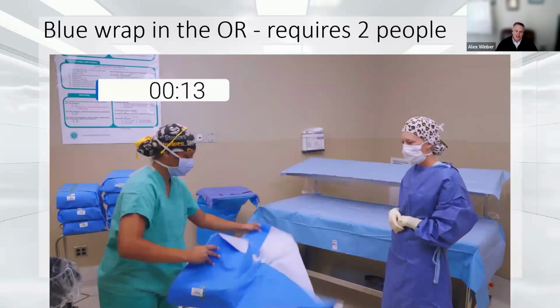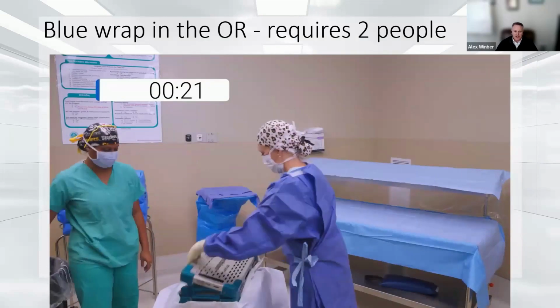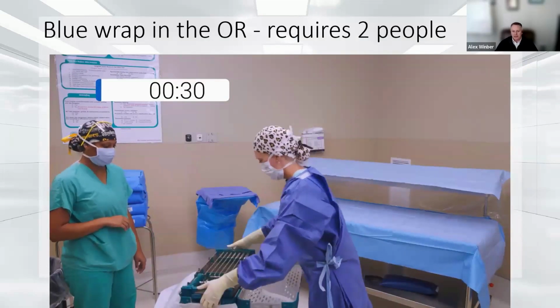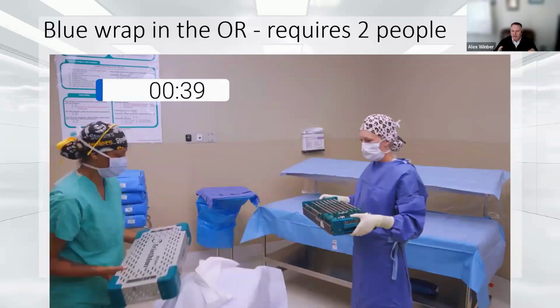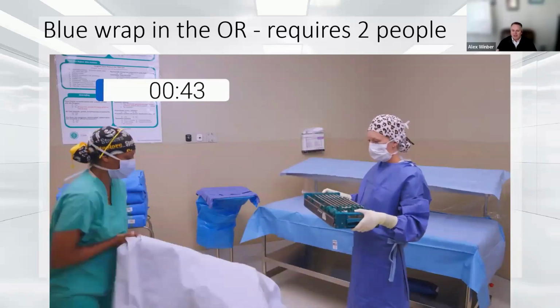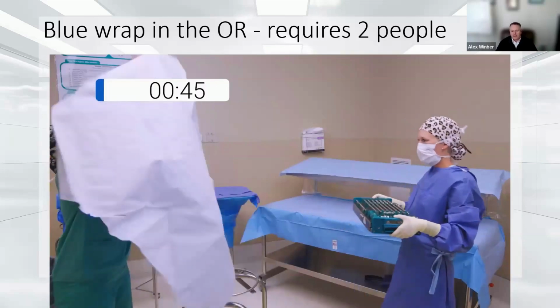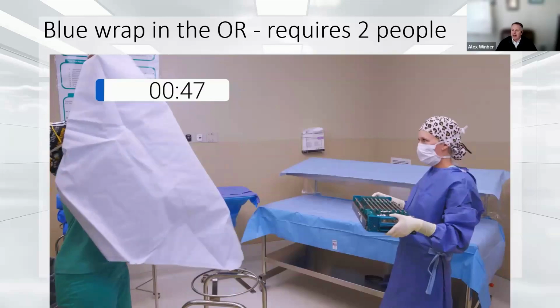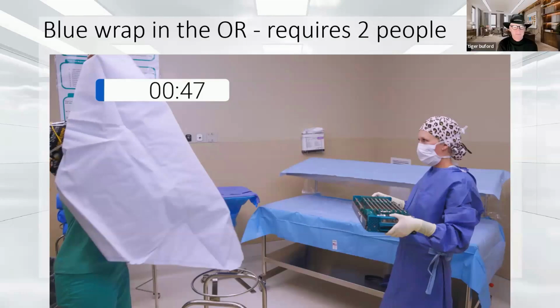So the person on the left is the circulating nurse, and she opens up the blue wrap, and then the scrub tech takes the tray out and she holds that tray, and these trays can weigh up to 25 pounds, and she holds it while the circulating nurse takes this big piece of blue wrap and holds it up to the light. She's supposed to do that for, I think, a couple minutes, but nobody ever does. They do it for 15 seconds. And for that reason, about 18% of the time, there are holes as big as the diameter of a pencil that are not found. Wow. So this takes a lot of time, but they're not necessarily finding the perforations that happen.